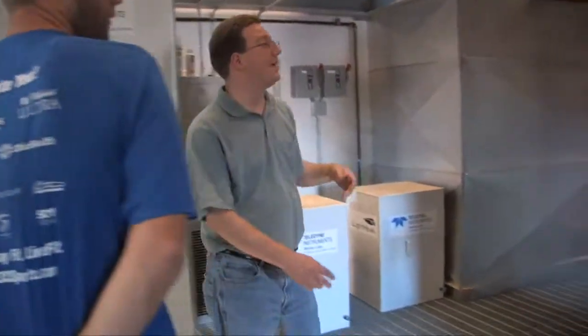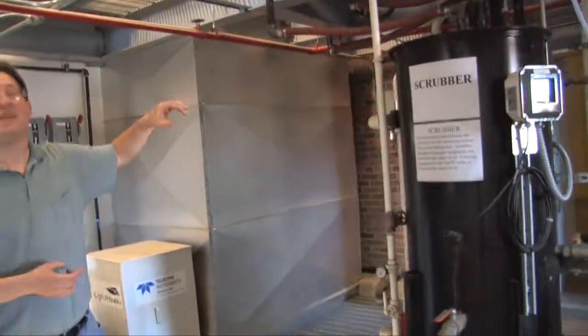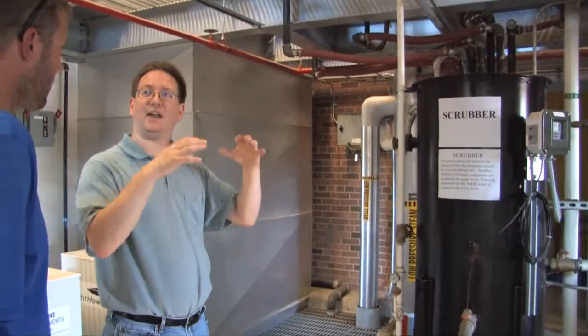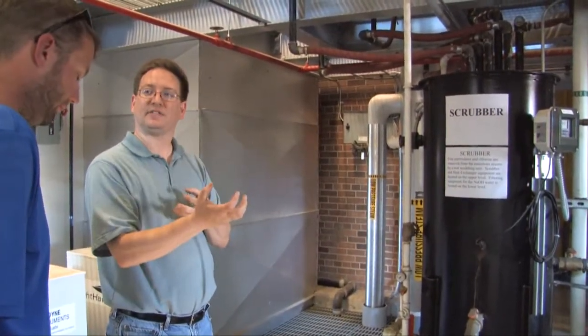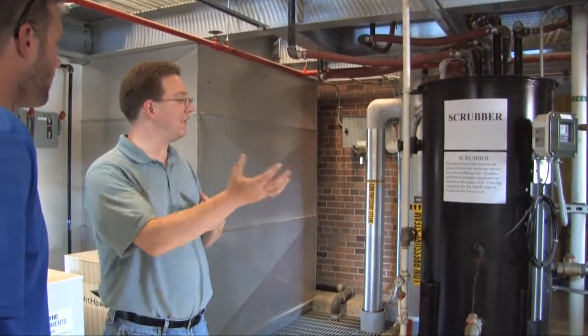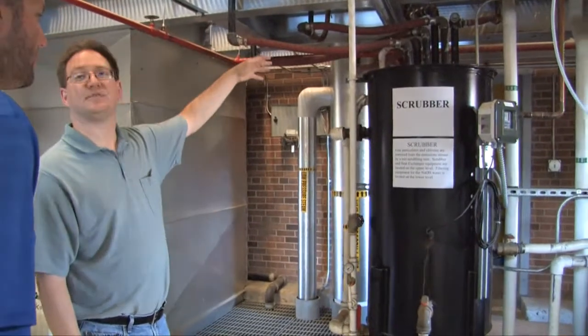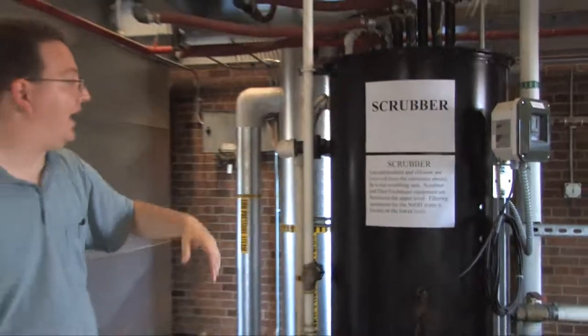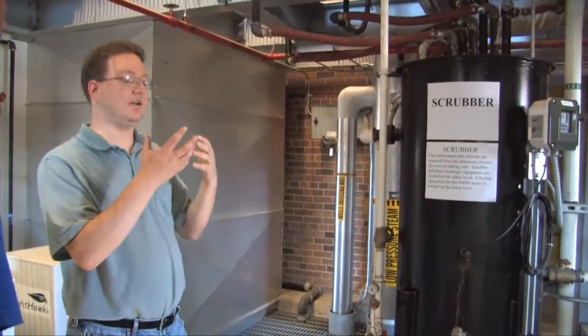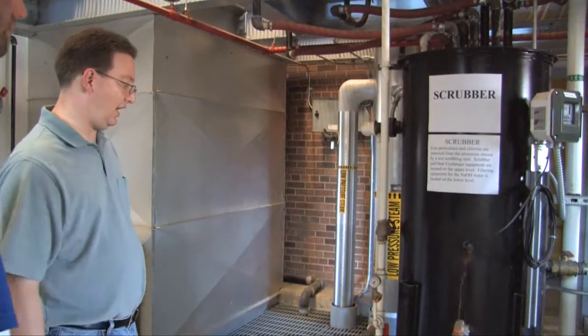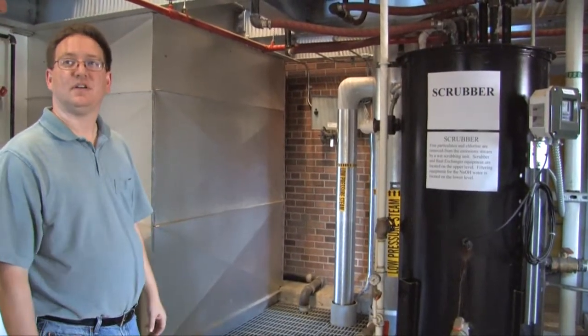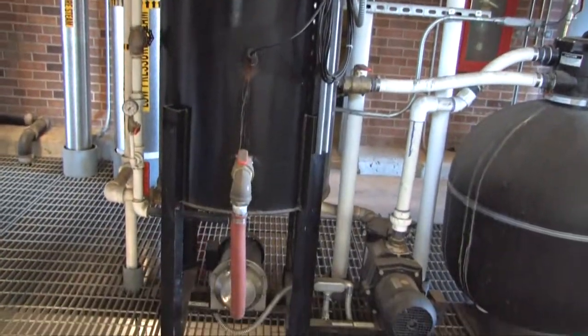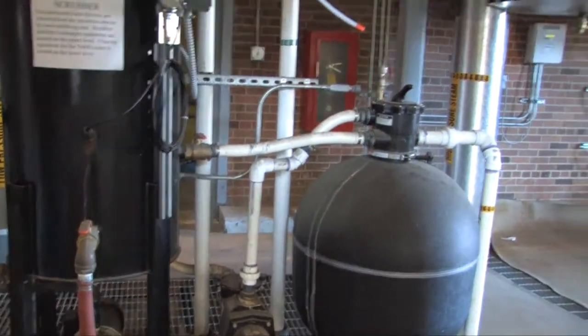So I talked about the sodium hydroxide. We have a wet scrubber unit. So the flue gas is coming through and there's a mist that's sprayed into it. And that mist will attract particles and it will attract the chlorine that's going through. And so what we do is we put in a small amount of sodium hydroxide. We've got a pH meter that regulates that. And then the water is sprayed in there and we produce salt is basically what the end product is. And then we also have a recirculating filter. And so we can send, every once in a while a purge itself and send the material down to them.